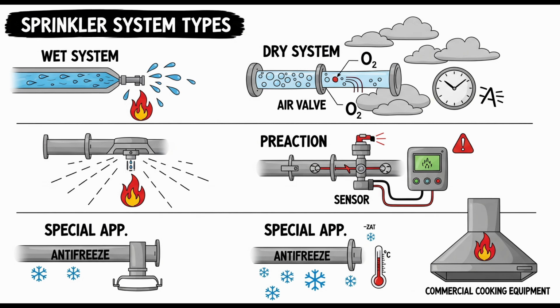Again, focused on preventing water from getting trapped where it can freeze. Upright sprinklers are generally fine because they naturally drain. Water just falls out. Right. Listed dry sprinklers are specifically designed for this application. They have a seal way back at the butt end, in the warm area, that prevents water from entering the unheated portion of the pipe until the head activates. Okay, those make sense. Built for the job.